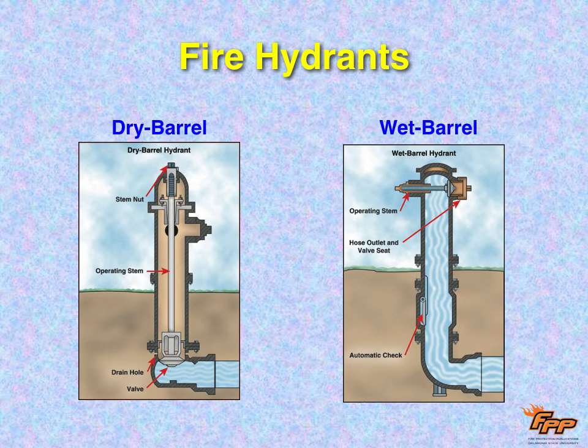Of course, in our communities, then, we're going to have fire hydrants, both dry barrel and wet barrel. And, you know, that's kind of obvious. Dry barrels are dry. The water is in the plumbing underground, and when you turn on the dry barrel, it fills the whole barrel with water. Now, you got to be aware with dry barrel hydrants when you become a firefighter. Once you open it, now it's open to the whole hydrant. So if you have multiple heads, you might want to connect a gated Y or something like that to the heads you're not using, because that way, if you need to connect more hose to the hydrant, you've got a way to do that.